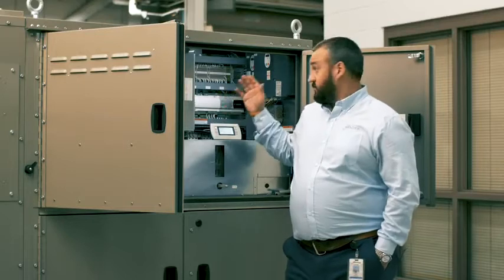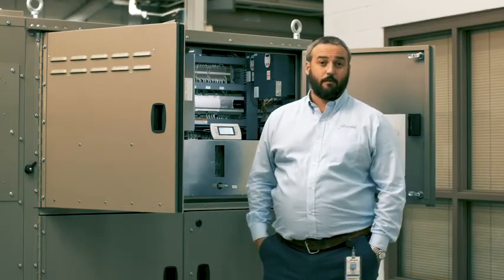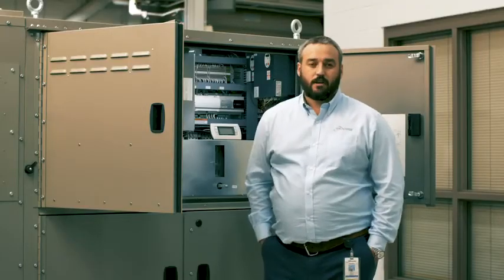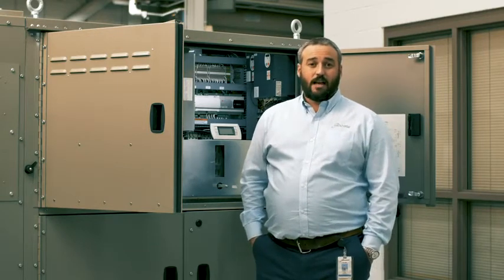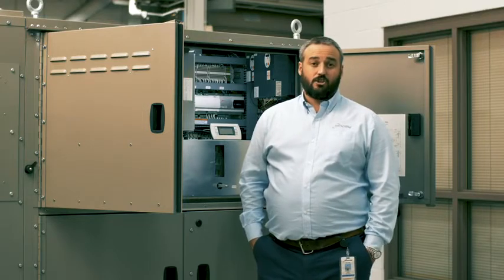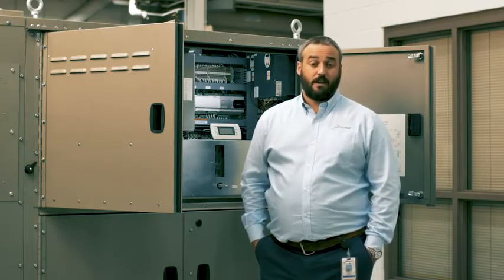Because we're pulling all of this information back to the controller, we decided that we would add the compressor operating envelopes into the software. What this means is by measuring condensing temperature and condensing pressure and evaporating temperature and evaporating pressure, we can plot where the compressor is actually running. And if it's outside of the safe operating zone for the compressor, we can shut off the cooling if it's been outside for more than 5 minutes. What we've done with this is we've put it on retry logic. So on the first alarm, the compressor will shut off and then automatically restart. But if you get 2 out of envelope alarms within 60 minutes, it locks out the cooling. You'd get that alarm over the BMS or through the handheld, and then the customer would have to come and clear the alarm and then investigate what the problem was.